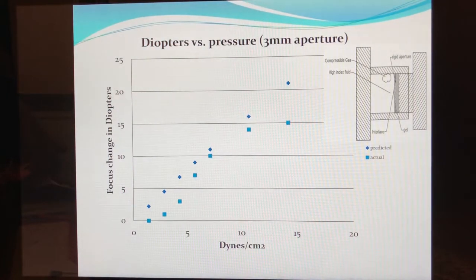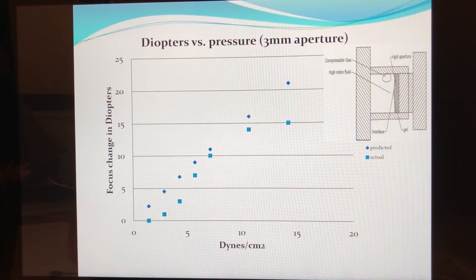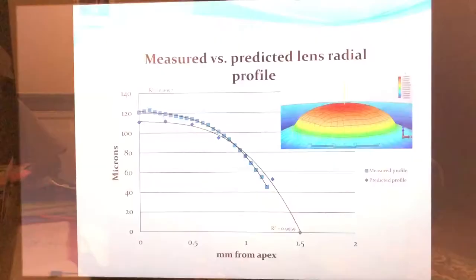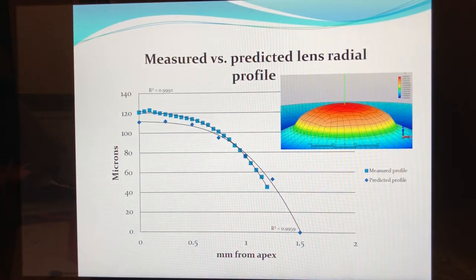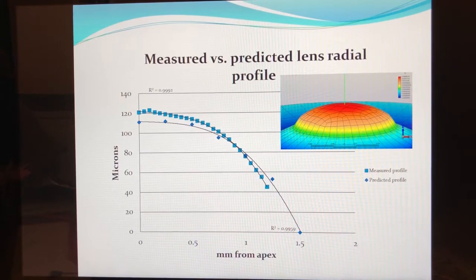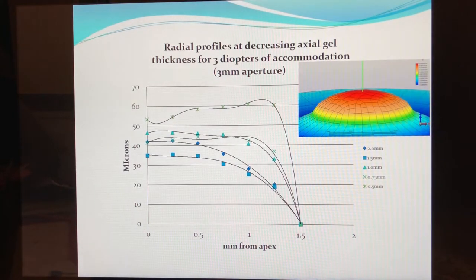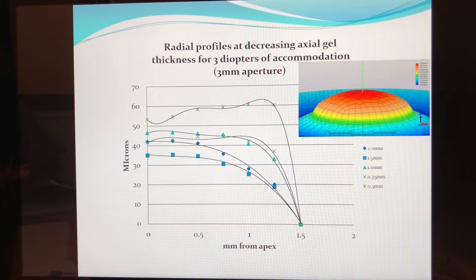Next we verify the model with the prototype. Here is shown the model-predicted and prototype accommodative change with applied pressure, which correlate fairly well. The actuation pressure is our first output metric. We then verify the contour of the interface, which is the refracting accommodative surface, with the prototype and again show good correlation between the prototype and the mathematical model. This slide illustrates that if careful attention is not paid to the design parameters, a nice refractive deformed surface can quickly degenerate into an aberration-producing machine.